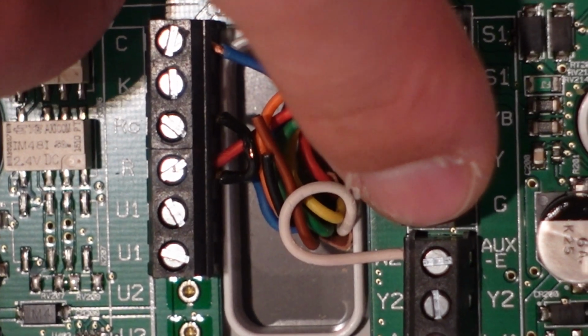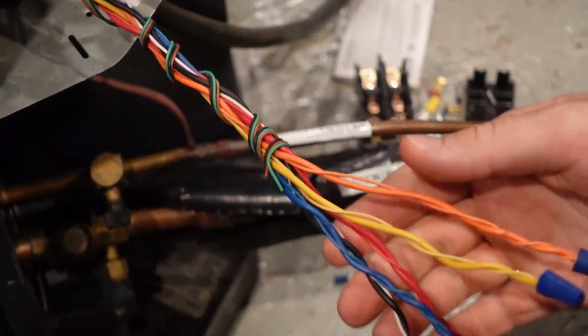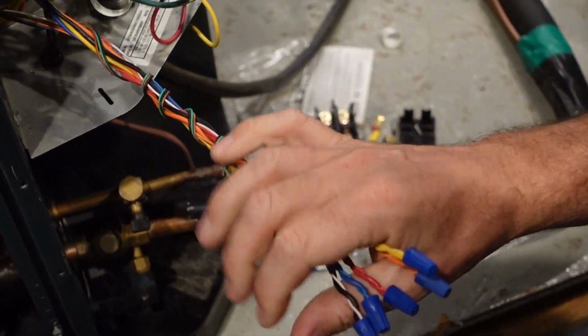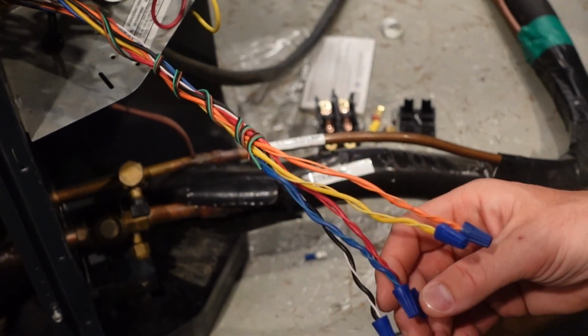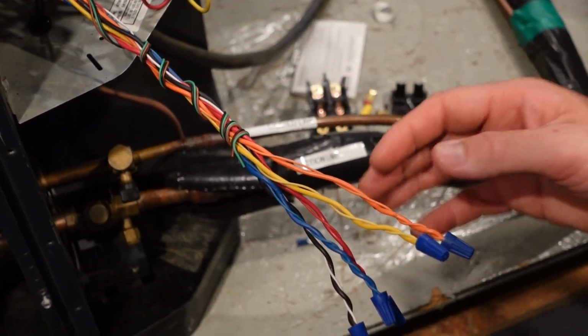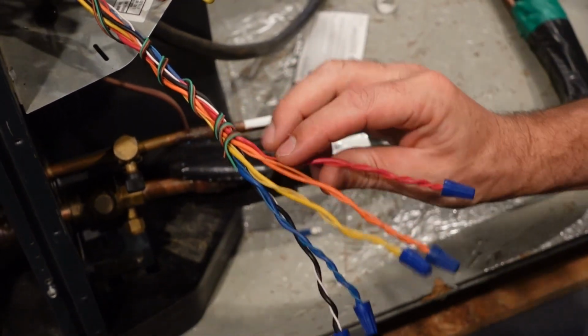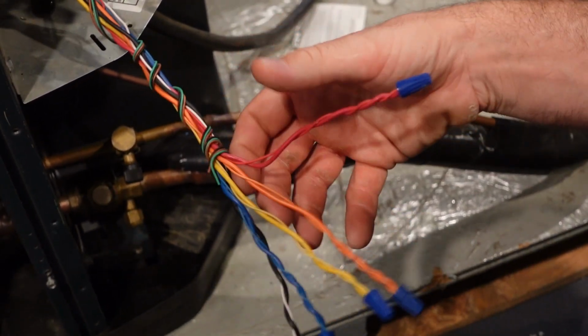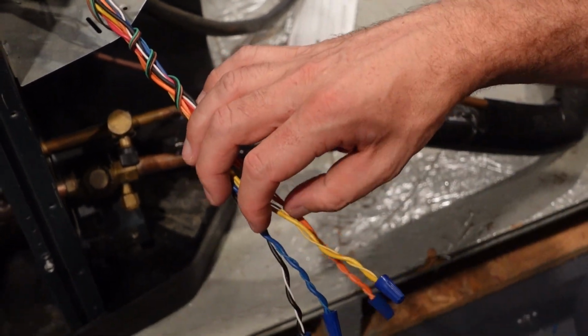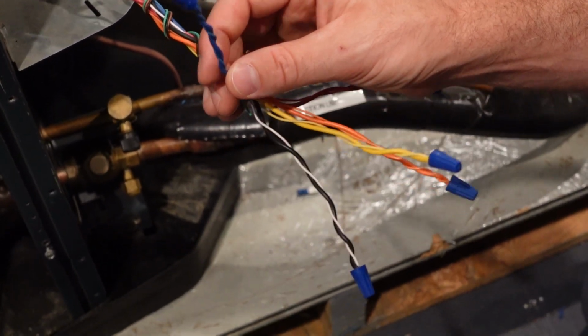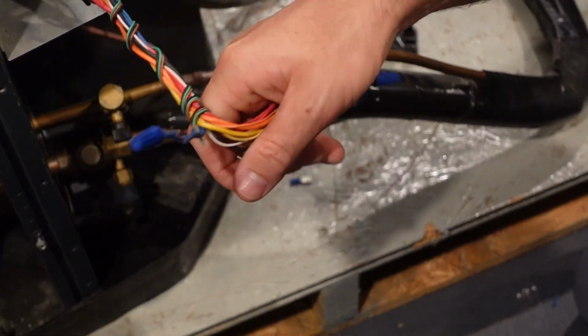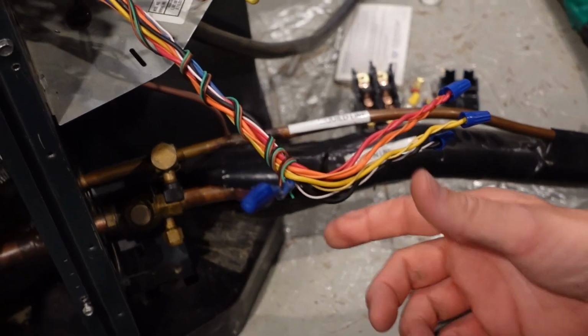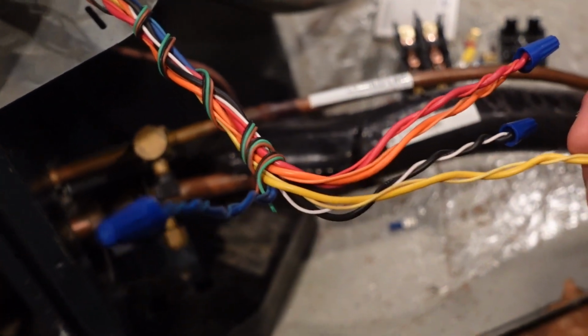Let's go to the outdoor unit. The first thing to take note of is where the low voltage comes in. Make sure you have plenty of excess wire so that you can easily get to these wires and diagnose the different voltages of what is actually happening here. So once again, we have our R terminal, which is our hot signal. We have our common terminal. We always check all of these to common. So think of it this way. Common is out here.